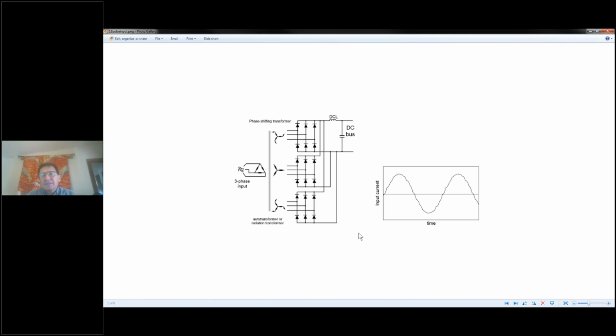The implications are this. You would have to go internally into the drive and rewire your diode bridges, which may be physically possible. On big drives, you're going to be dealing with big conductors, possibly bus bars, but you're not going to be able to do it under UL 508, obviously, because you're in the field. So please be aware of that. I hope this allows you to avoid stepping in the gopher hole, if you will, when you go to retrofit some of these 18 pulse systems, many of which were installed in the 90s and early part of the century and are definitely coming to end of service life.